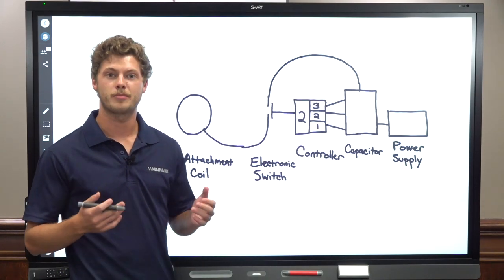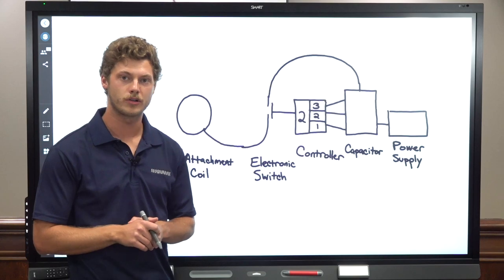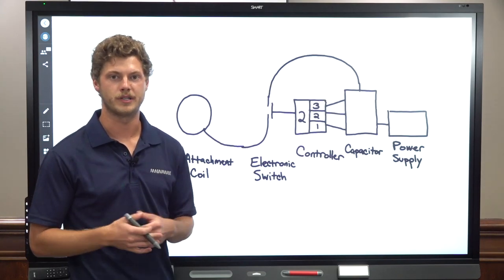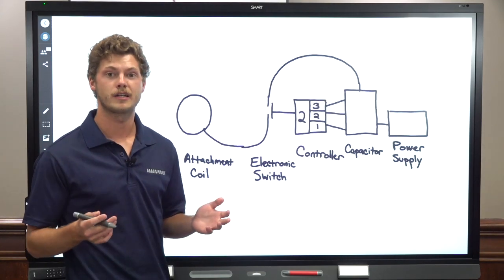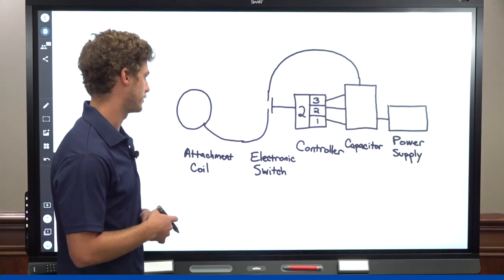As you can see, for a higher power setting, the capacitor will take longer to charge up and there will be more time in between each pulse. A lower setting would pulse more frequently and take less time to charge the capacitor.